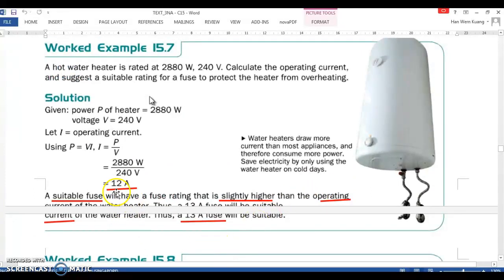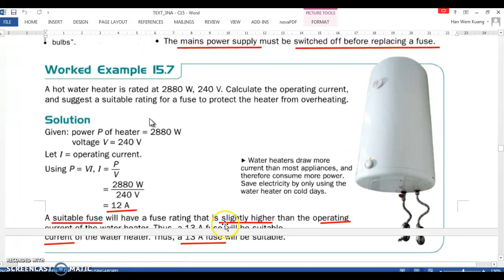So if I use P equals VI, and the current works out to 12 amperes, the suitable fuse will be 13 amperes—always slightly bigger. Of course you don't use something like a 26 or 30 ampere fuse, because while that fuse could withstand such high current, the cables connected to your appliance may only operate at 13 or 14 amperes. If you bumped it up to 30 amperes, even when there's a fault the fuse would still allow that current through, which isn't very good.